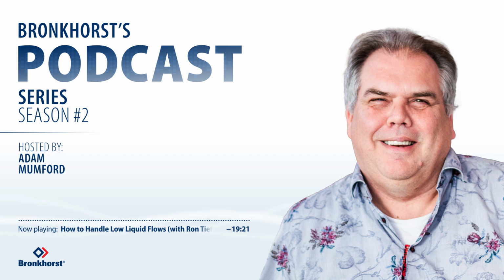Yeah. You've mentioned metering the flow, so that's just pure measurement. And you've also mentioned, Ron, controlling the flow rate, which is obviously more of a challenge. So what do we use at Bronkhorst as the main principles when it comes to controlling liquids? Again, it depends on the conditions. If you have enough pressure and a very stable pressure, then a valve would be preferable because a valve is more stable than a pump. If you have a stable inlet pressure, of course, a valve is much faster in response than a pump.